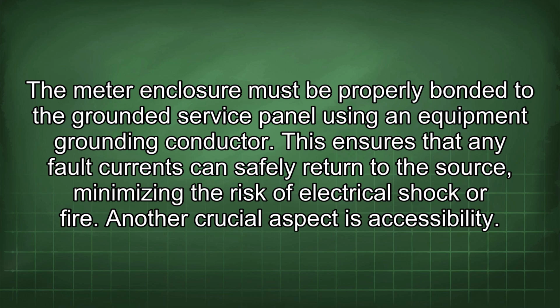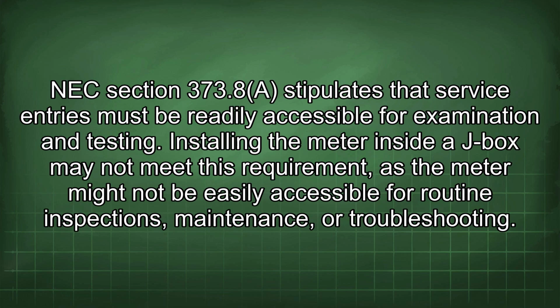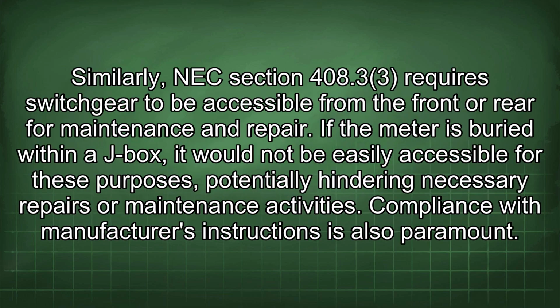Another crucial aspect is accessibility. NEC Section 373.8 stipulates that service entries must be readily accessible for examination and testing. Installing the meter inside a J-box may not meet this requirement, as the meter might not be easily accessible for routine inspections, maintenance, or troubleshooting. Similarly, NEC Section 408.3(3) requires switchgear to be accessible from the front or rear for maintenance and repair.